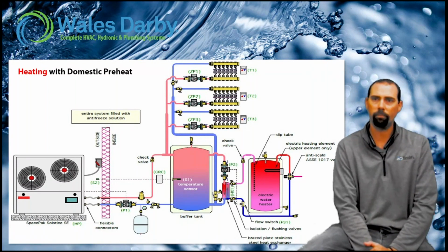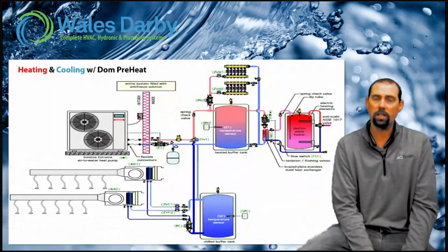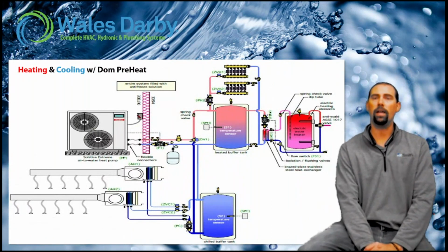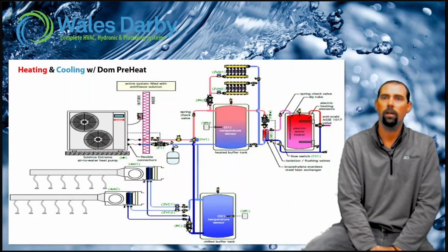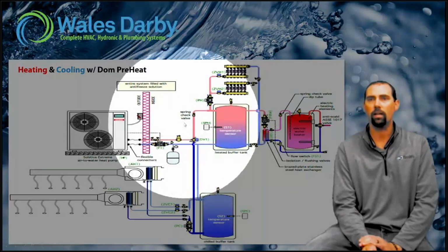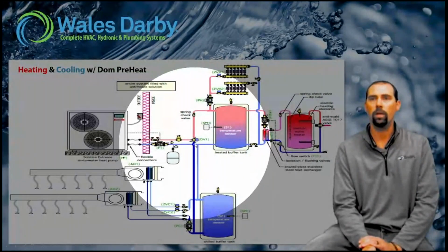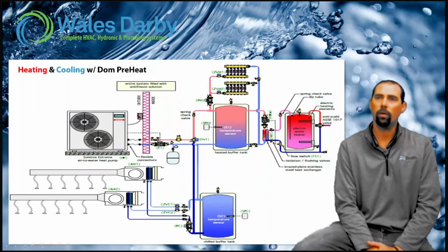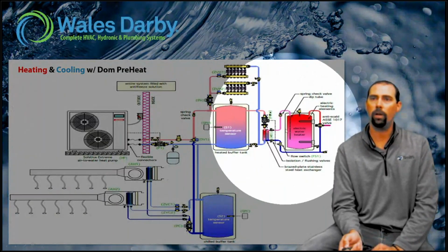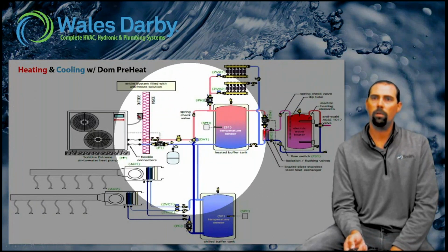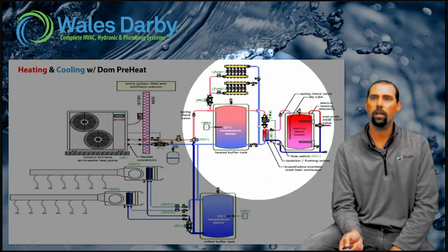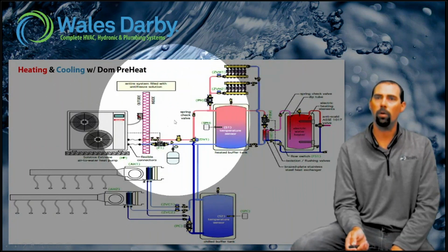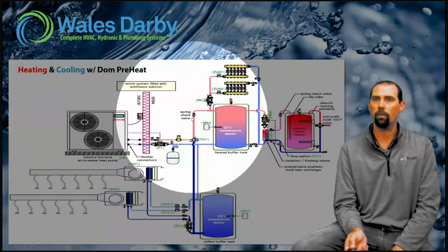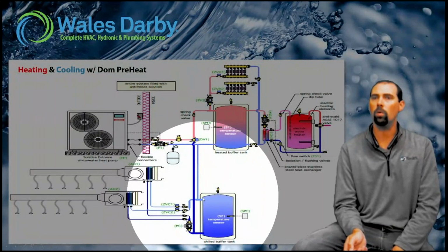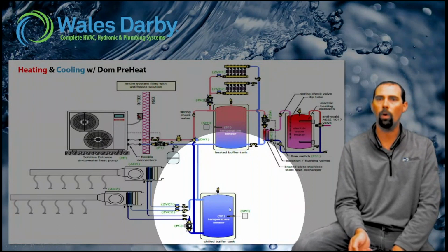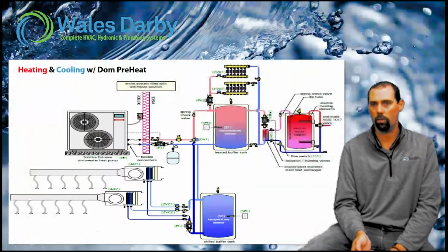This is really the way to combat that. So on the heating side, we could just add a second buffer tank. Now we have a heated tank and a cooling tank, just by adding a tank and a 3-way diverter valve. If we had a DHW call, we'd need to get some tank temperature up in there electrically - this little valve is just going to divert its way and put all its heat into that tank, and we'll get that signal out to the heat pump to go into heating. Then once we're done, we'll switch that reversing valve, go into cooling, and now we can supply the lower temperatures, 42, 44 degree water, into this tank and satisfy our cooling air handlers.